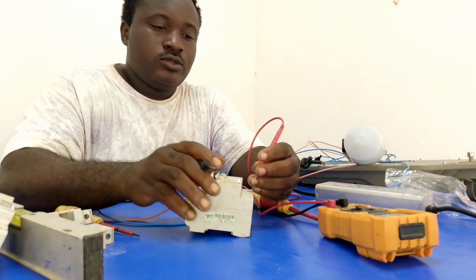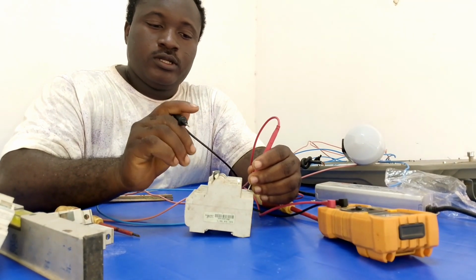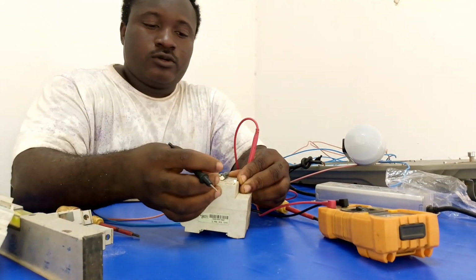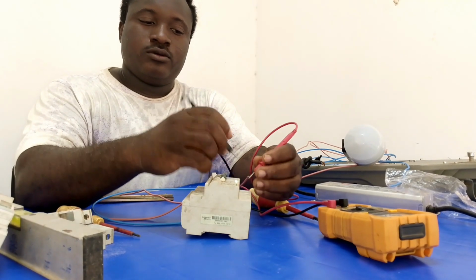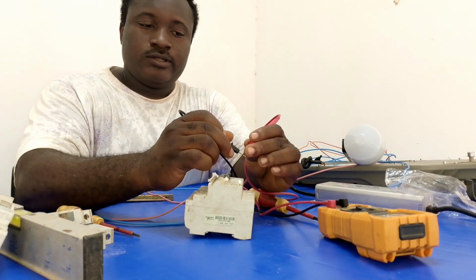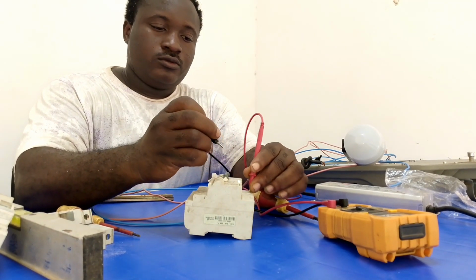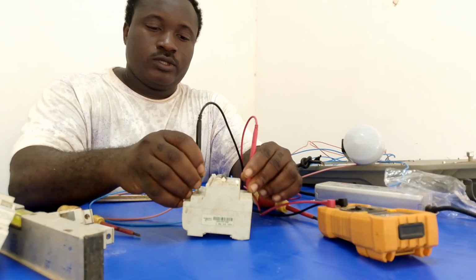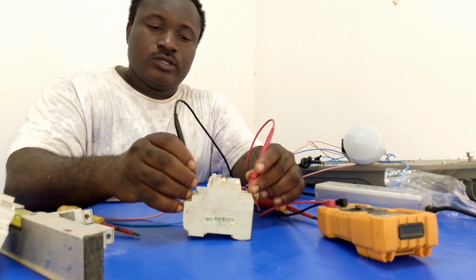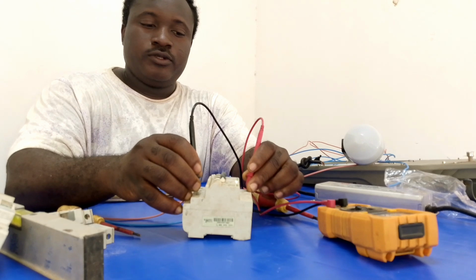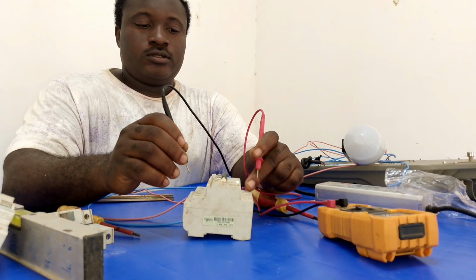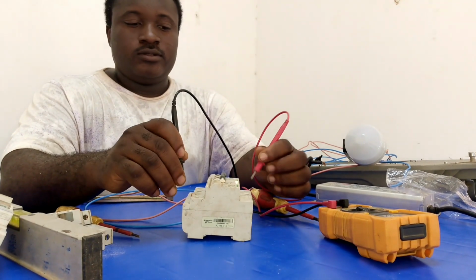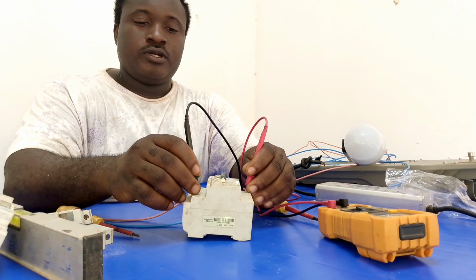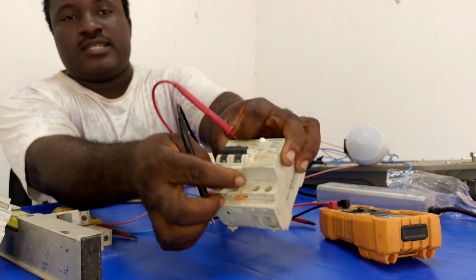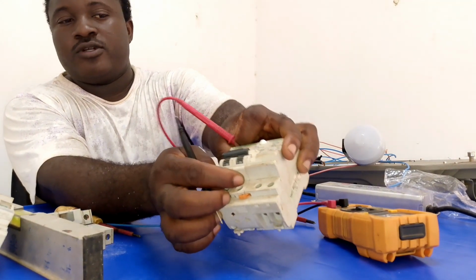Check continuity to see which one is the neutral and which one is the line. When you check continuity, you have to put the RCD on. Now that the RCD is on, check from here to one terminal here. So this one is the neutral, this is in and this is out. So this is our neutral. You can see the neutral sign is there, but you have to check before you connect it.